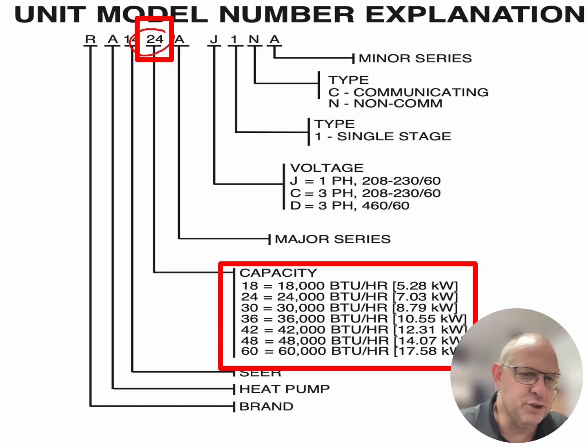R tells you the brand, it's a Rheem. Heat pump, A. 14 tells you the SEER rating of it. 24 tells you the BTU capacity, and then the major series is A. We look at the voltage of this one, and we're dealing with 208, 230, 60 hertz. So it must be an American unit that they're putting out. And then type 1 single stage.